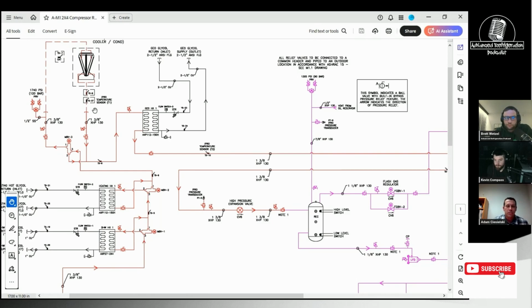And that is entirely based off of the density of that liquid, or whether it's transcritical, whether it's liquid or supercritical in this state. The density is so high that it may even be a supercritical state, but the density is very comparable to a liquid. So if you were to size that pipe based off of a liquid, which we're used to doing, the erosion effects of that copper would be greatly increased.